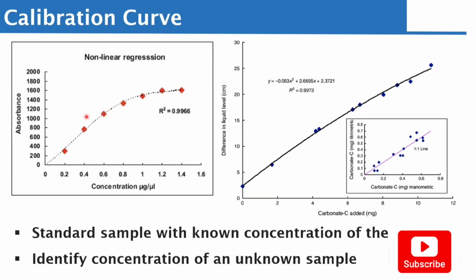it means that the analyzer that has this curve can only measure something between 0.2 to 1.4. That's what it's trying to tell you. If anything is higher than 1.4, it cannot measure it. If anything is less than 0.2, it cannot measure it. Now, let's go to this other one. If you look at this one, you're going to see that the concentration here started with 0. You can see that there's a 0 here.